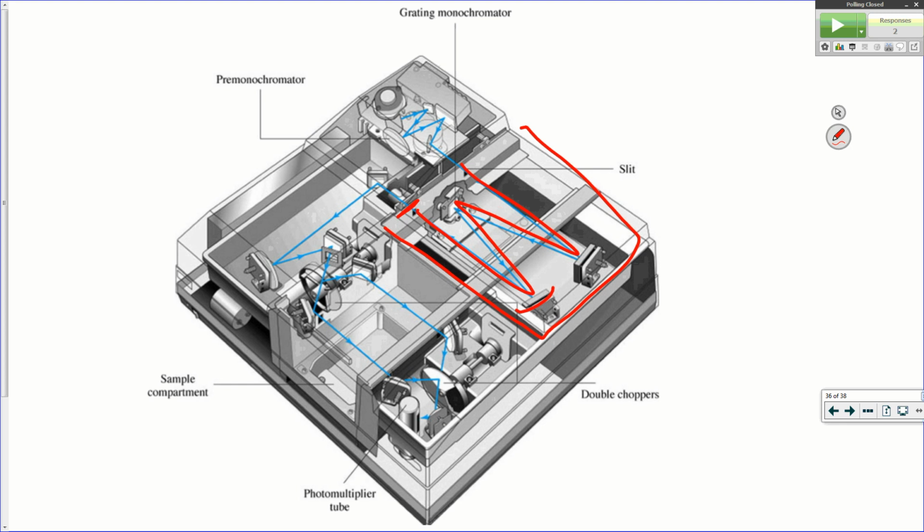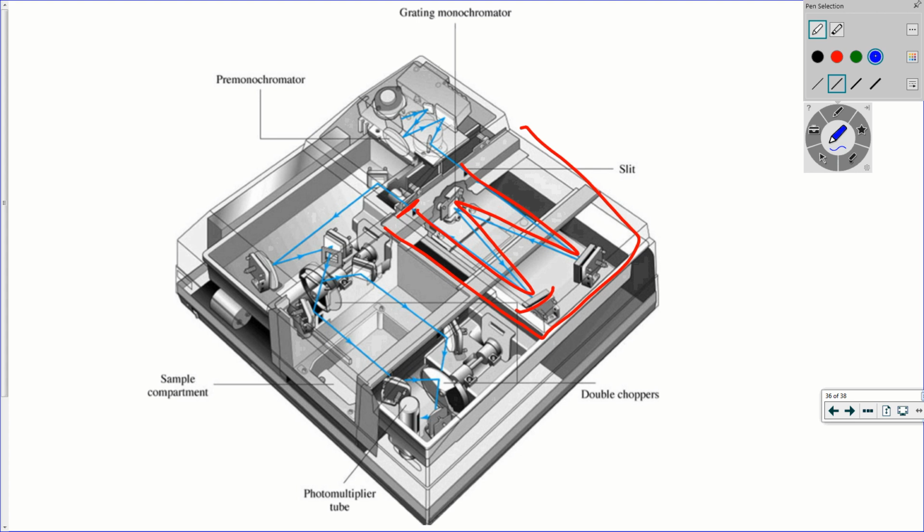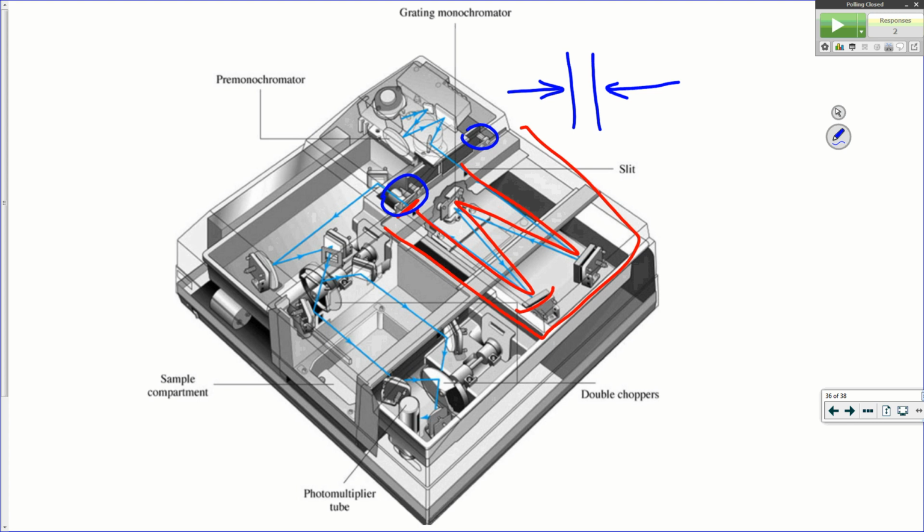On this style of instrument, the slit widths are adjustable, so there are servo motors that control exactly how wide these slits are, and those go back and forth with high precision and adjust that. Typically, they're going to work in pairs. But the light's bounced all around through those things, and every one of these mirrors has to be very, very securely attached so that there's no movement. If a mirror were to shift because the instrument's bumped, everything is out of alignment.